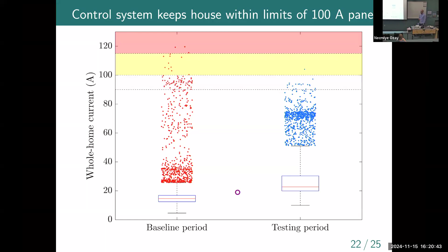We don't know of any devices currently doing this that are approved in the field, but there is a provision in the National Electrical Code that says you can use software in place of a current limiting device. We found this after doing the experiments, but it requires lowering the limit to 80% of the panel rating—so rather than shooting for 100 amps, we'd have to shoot for 80 amps, which we exceed significantly. With better control and logic we could probably knock this distribution down below 80 amps, but as it is this wouldn't be sellable.